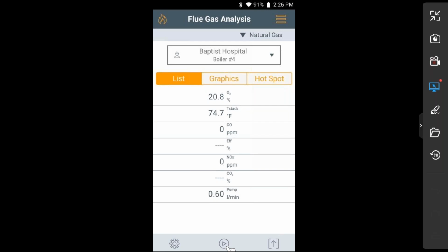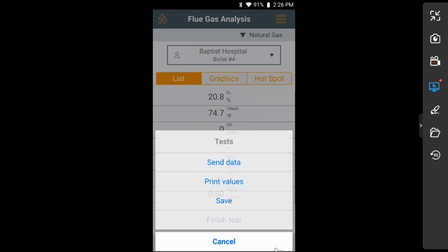You're in the flue gases, and on the bottom here, you'll see a gear, a service gear. This is my pump, on and off pump. And this is where, if I press that button here, I have the capability of sending my data through Wi-Fi. I can print to an IR or to a Bluetooth printer. These instruments come with or without Bluetooth printers, and you can save the readings, as I said, internal to the instrument.